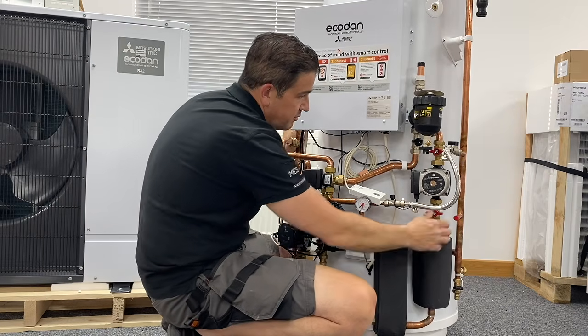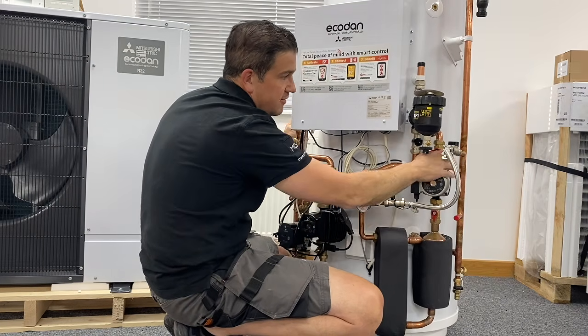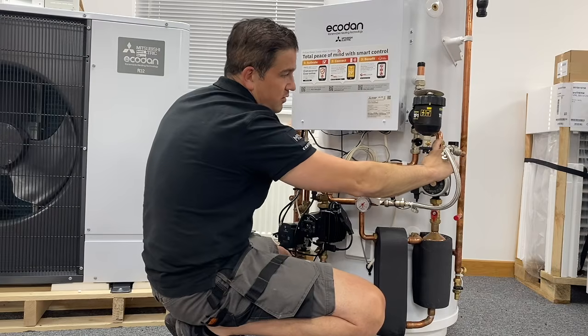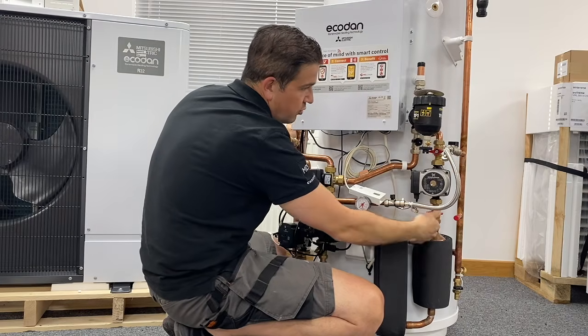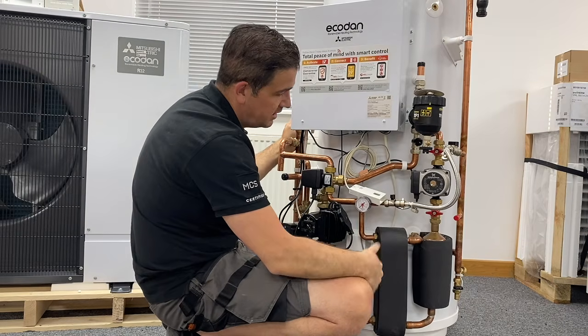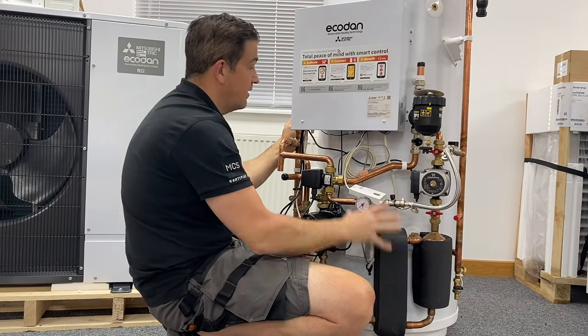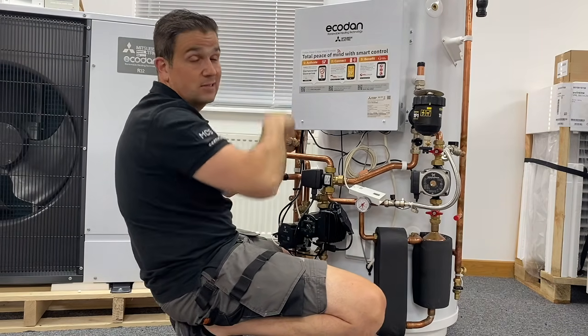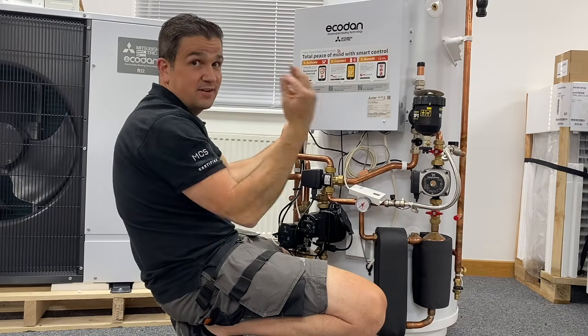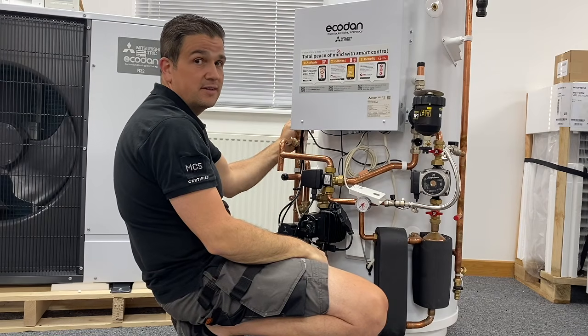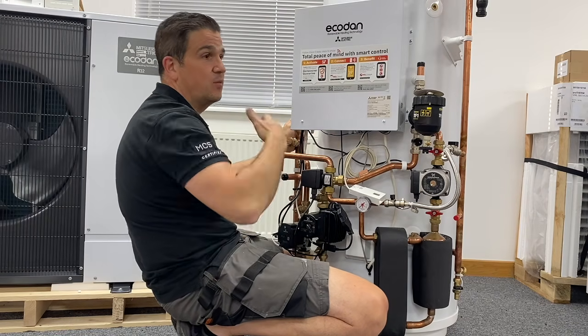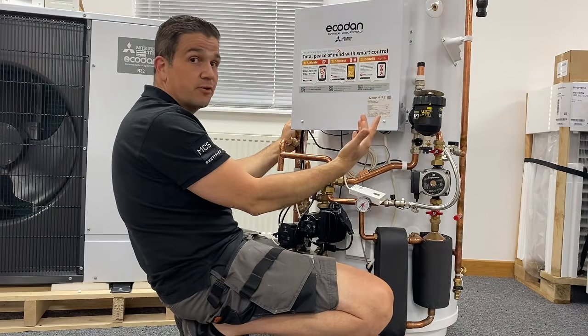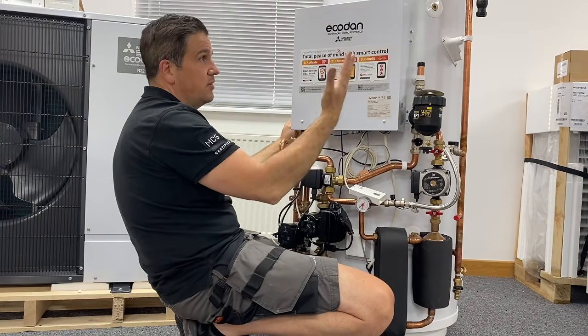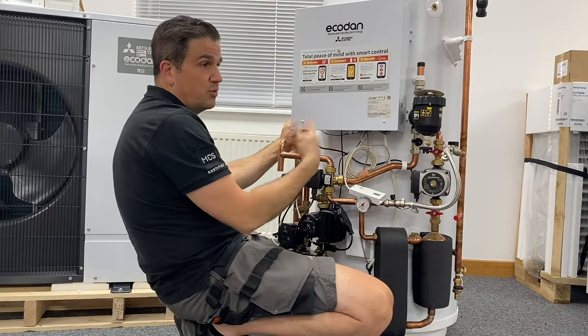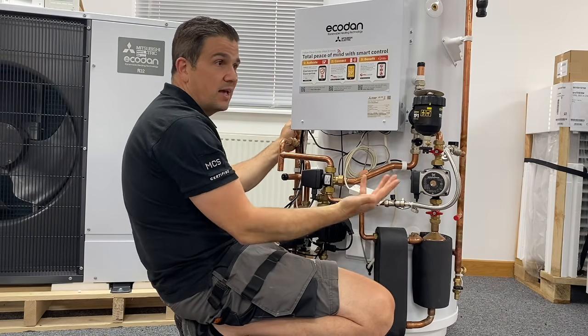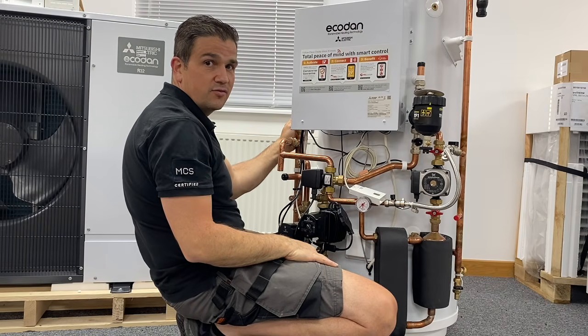So obviously you must make sure that both of these are in the on position when putting your hot water on. And that's basically what you'll get. It also means that the capacity of the cylinder is the capacity of hot water that you're getting. What I mean by that is that when you put a coil in there, it's going to take up some room. So you might have, say, 210 litres, but with a coil inside you might only get about 185 litres of hot water in there.